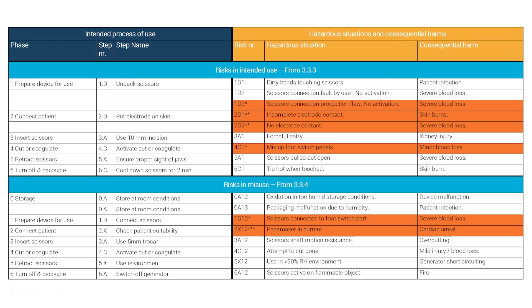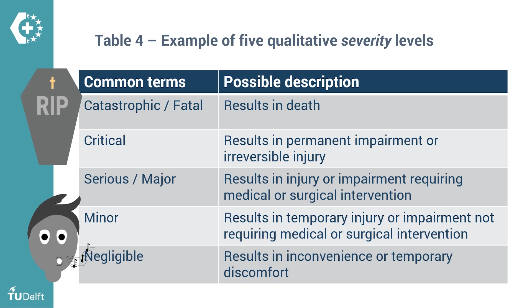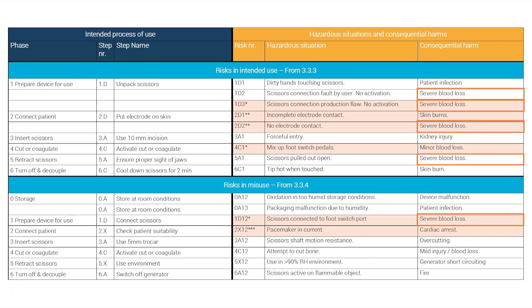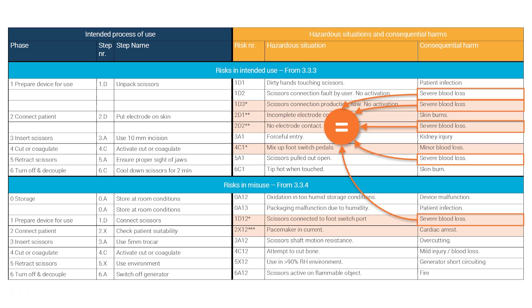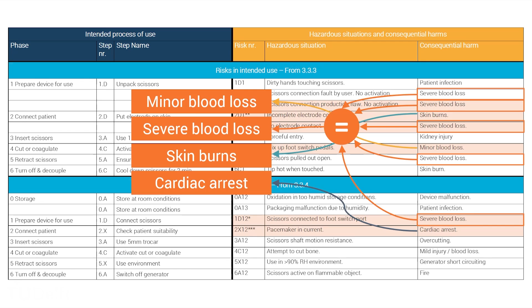For each of our selected harms, we will have to define what severity level it is. For this case, we will use the severity levels from an example in ISO TR 24971 Table 4. It has 5 qualitative severity levels going from negligible, when it results in nothing more than inconvenience or temporary discomfort, to fatal if it results in death. In our selected risks, we see severe blood loss several times, so we can treat those together. This nicely illustrates how choosing consistent terminology will make your risk analysis more efficient. Now, this leaves us with 4 unique harms: minor blood loss, severe blood loss, skin burns, and cardiac arrest.